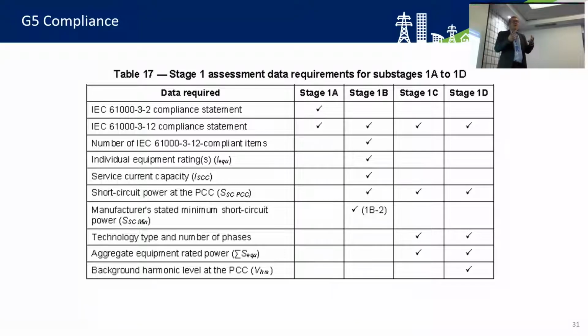So when we go out and measure background, we have what's known as power quality recorders. For any voltage complaints, flicker complaints, or harmonic complaints, we'll connect this power quality recorder. It measures everything - we don't set it to just measure one thing. And over the last couple of years, for the first time, we've been seeing higher levels of harmonic emissions on the LV network.